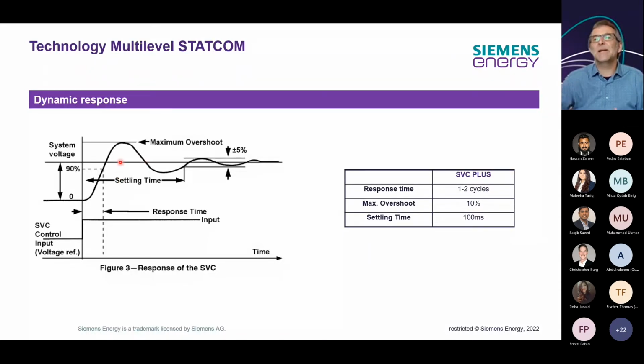Otherwise, if you have the same parameters applied and the grid would be strong, you would have a massive overshoot, which we don't want. Or the other way around, if you would assume there is a weak grid, but it is a strong grid, and you apply less power from the converter, you would be very slow. So in other words, you want to optimize the speed of response and the minimum of overshoot.